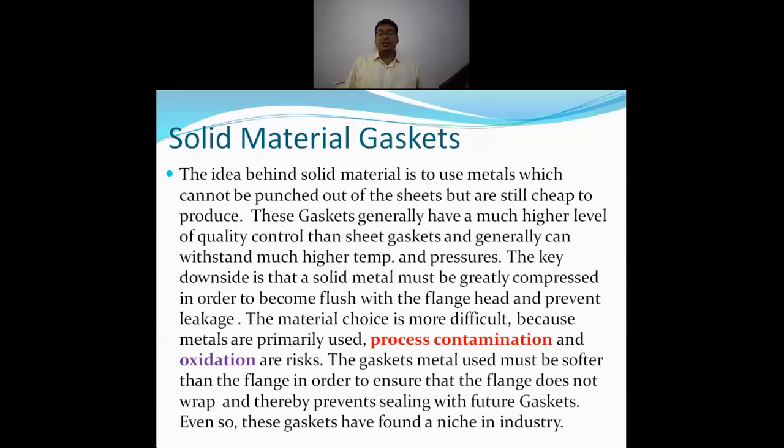These gaskets generally have a much higher level of quality control than the sheet gaskets and generally can withstand much higher temperature and pressure. The key downside is that the solid metal must be greatly compressed in order to become deformed and fluid, to make it flow.